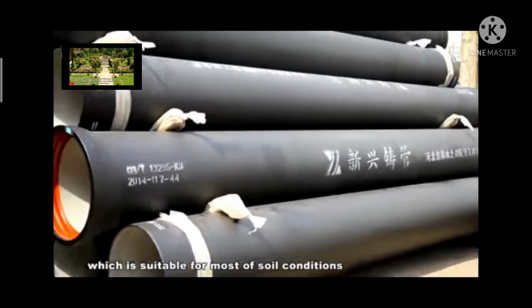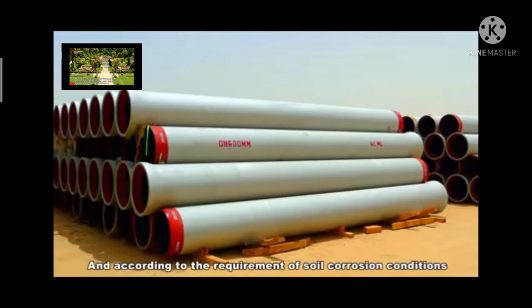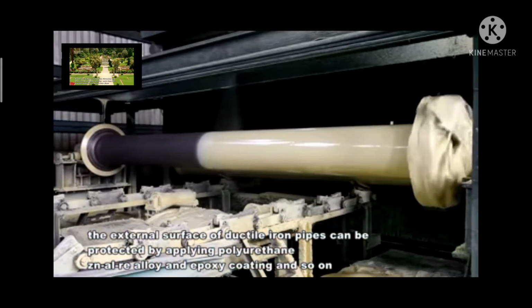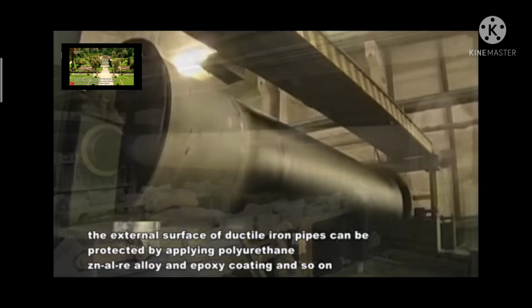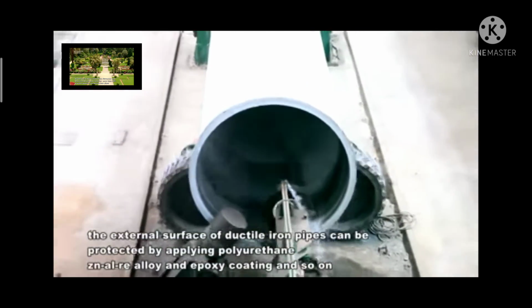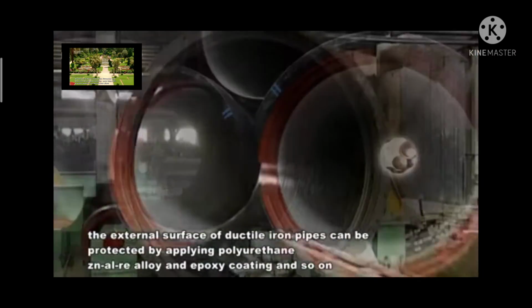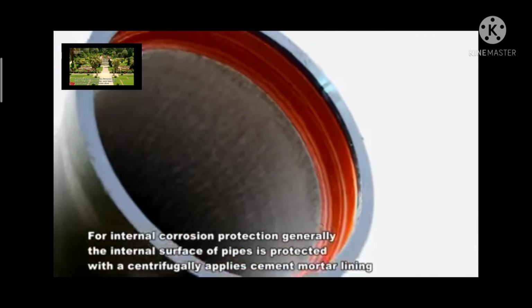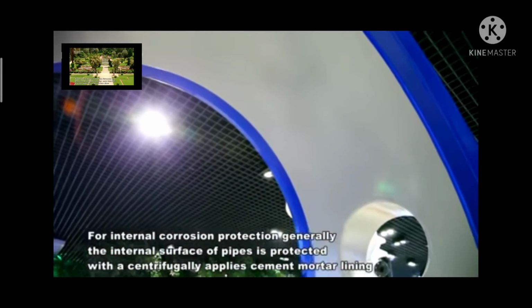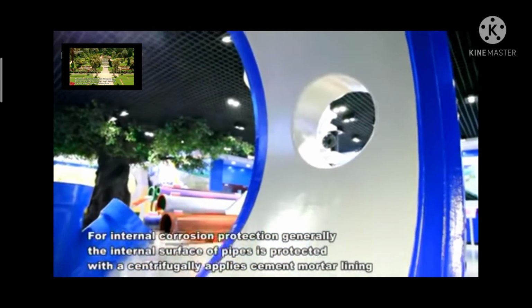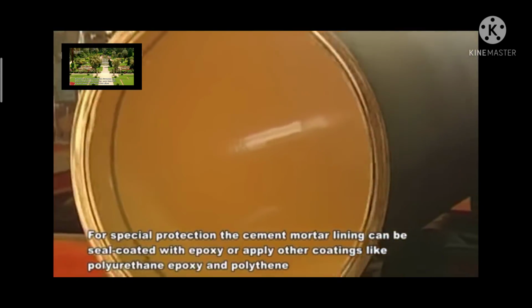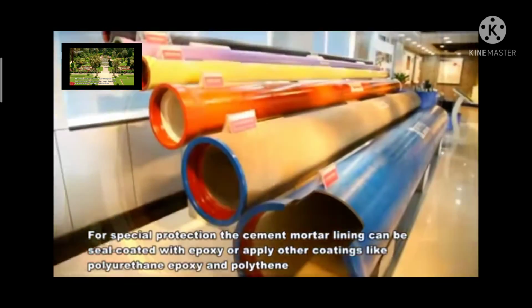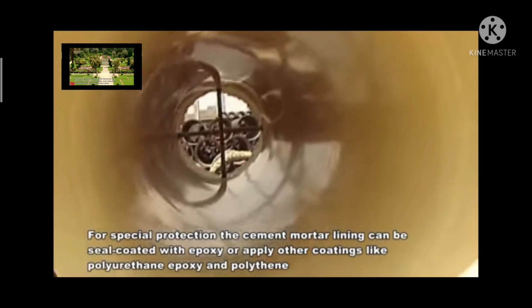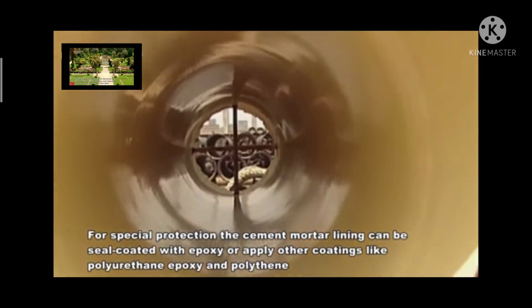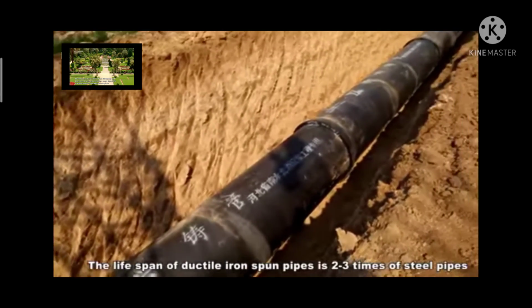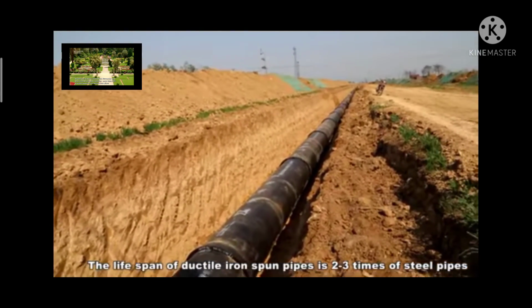According to the requirements of soil corrosion conditions, the external surface of ductile iron pipes can be protected by applying polyurethane, ZnAlRe alloy, epoxy coating, and so on. For internal corrosion protection, generally, the internal surface of pipes is protected with a centrifugally applied cement mortar lining. For special protection, the cement mortar lining can be seal-coated with epoxy, or other coatings like polyurethane, epoxy, and polythene can be applied. The lifespan of ductile iron spun pipes is 2 to 3 times that of steel pipes.